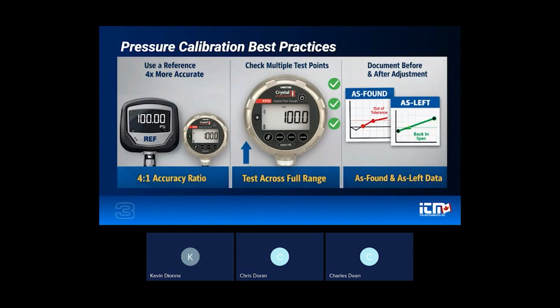So once calibration frequency is defined, the next step is making sure the calibration itself is done correctly. One of the most widely accepted best practices is using a reference standard that's at least 4 times more accurate than the device under test. This ensures the calibration results are reliable and reduces uncertainty in the measurement. Calibration should be performed across the full pressure range, not just a single point. Pressure instruments don't always drift evenly, so checking multiple test points allows you to catch any non-linearity that might be going on.